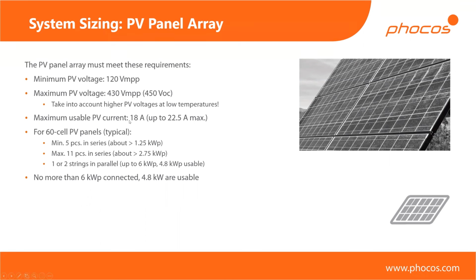Then we have a maximum usable PV current of 18 amps. So in practice, it just means 1 or 2 strings, and that's how you build your system. For each string, you have a minimum of 5 PV modules if you're working with 60-cell crystalline PV modules. So that means your minimum power for the 5 kilowatt unit is about 1.25 kilowatt peak, and the maximum is 11 PV modules in series. If it's really warm in your region, you never have cold winters, you might be able to fit in 12, but that's living at the edge basically. So I would recommend up to 11.